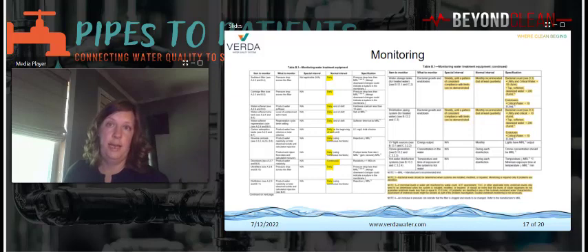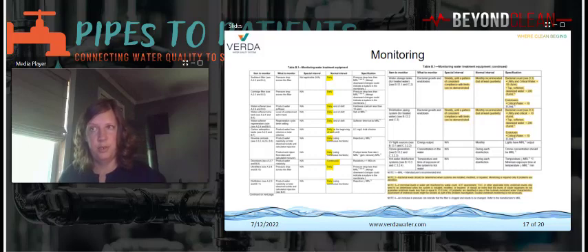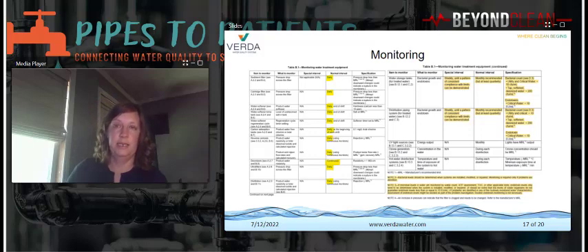Appendix B in AAMI TIR 34 gives methods for monitoring water quality treatment equipment. This ensures the equipment is inspected and maintained to give optimal performance. Monitoring can be done by maintenance personnel or reprocessing personnel. The water can be manually tested or measured using inline continuous monitors. Many options are available and will vary depending on the equipment that's installed.